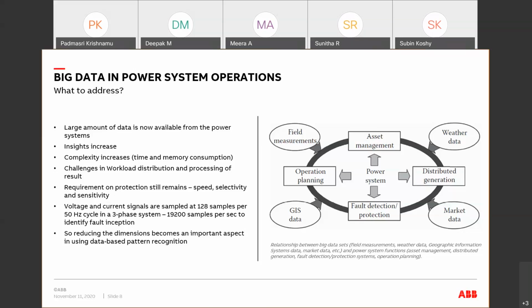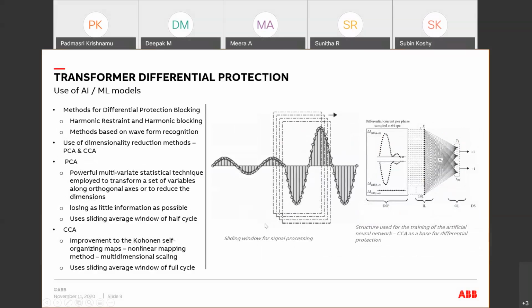Now let us concentrate on one of the use cases, that is, transformer differential protection. Let us consider the power transformer and its traditional protection requirement. The main protection used in a power transformer is the differential protection, which is based on Kirchhoff's law of electric circuits. This protection scheme has excellent performance in detecting internal faults, but it can operate incorrectly due to magnetic saturation in current transformers caused by the DC component present in the fault current.